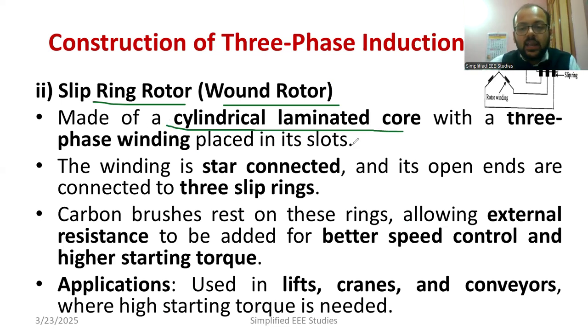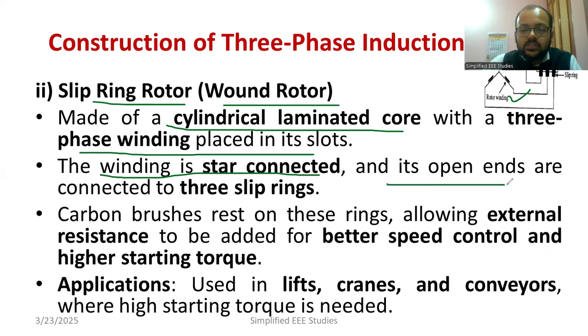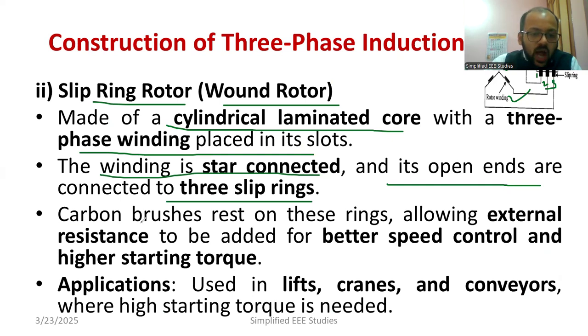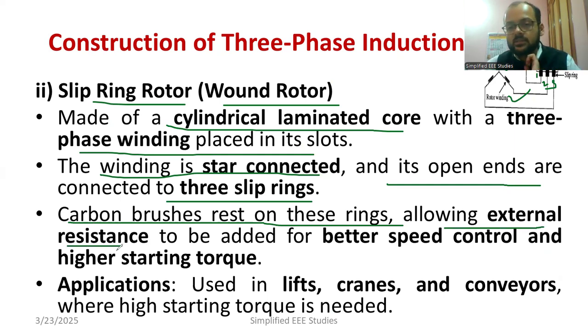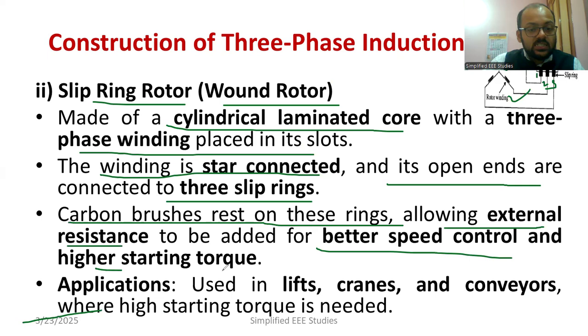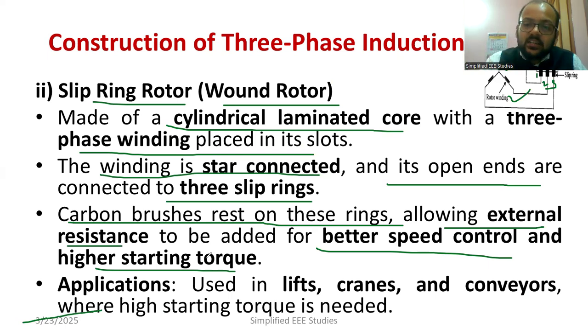A slip ring induction motor is made up of a cylindrical laminated core with three-phase windings placed in its slots. The winding is star connected and linked to three slip rings. Carbon brushes rest on the rings, allowing connection of external resistance. It is suitable for better speed control and higher starting torque applications. However, the major setback is that as external resistance increases, losses also increase and efficiency drops.